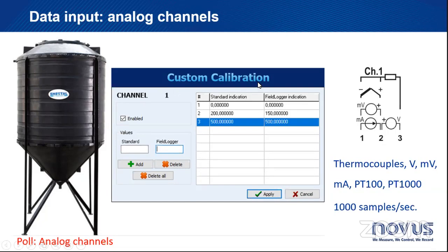So what the field logger does is basically you write down what it's reading and what it should be reading, and add. You're allowed to add up to 10 points here, okay? In most cases, you don't need those 10 points. You need just a couple, but in other cases, you will add as many points as you can on the most non-linear part of your curve, okay? So this is one example.